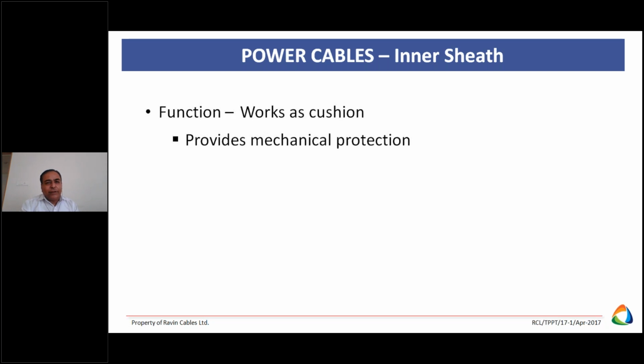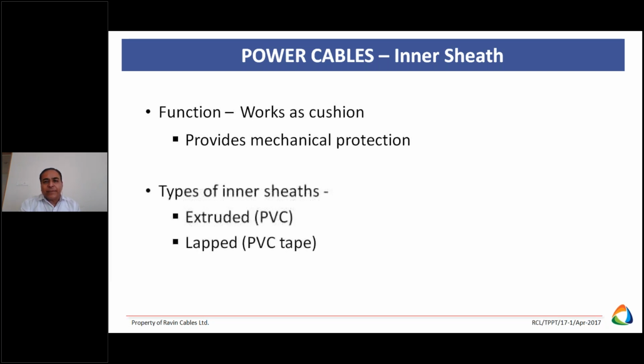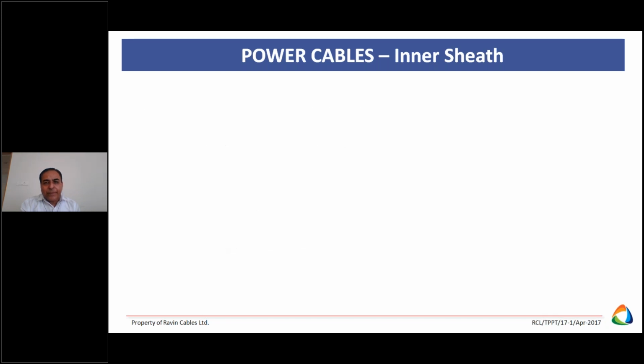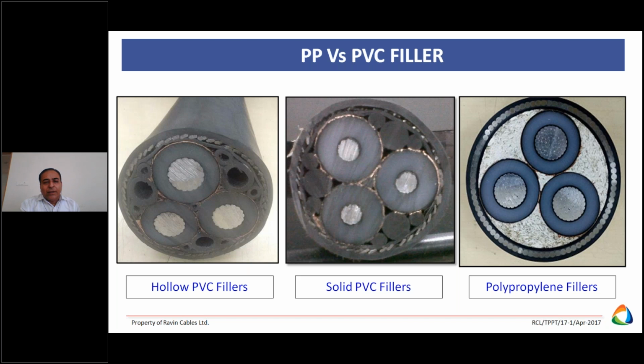Sir, excuse me. Yeah, please. Sir, you are showing this. Actually, my doubt is what is the range of voltage this cable can withstand, sir? Basically, cables are designed for different voltage grades: 1.1 kV, 11 kV, 33 kV, 66 kV, 132 kV, 220 kV, 400 kV, even 800 kV. For voltage withstanding, you have to decide the voltage of your system.